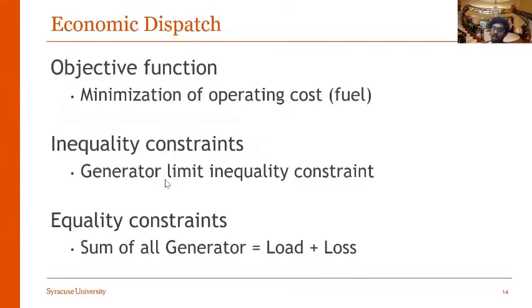Some of these constraints are generator limit inequality constraints, which means you cannot produce more than a specific amount of power for a given generator, nor can you produce less than a specific set point. For the entire power system, you have to make sure the sum of all power generated equals the demand of the load plus line losses.